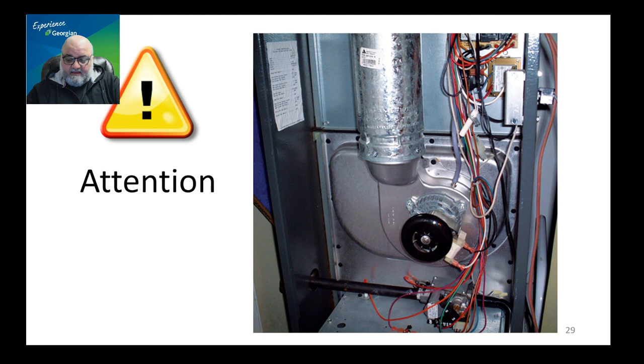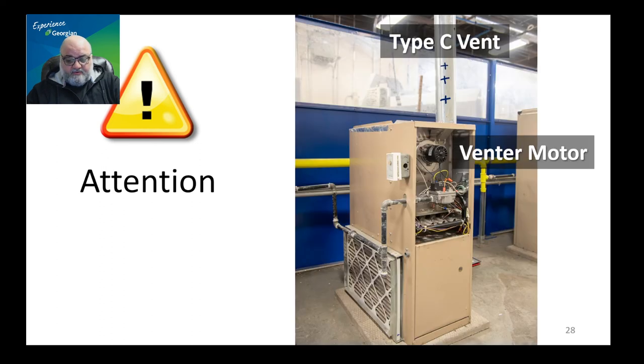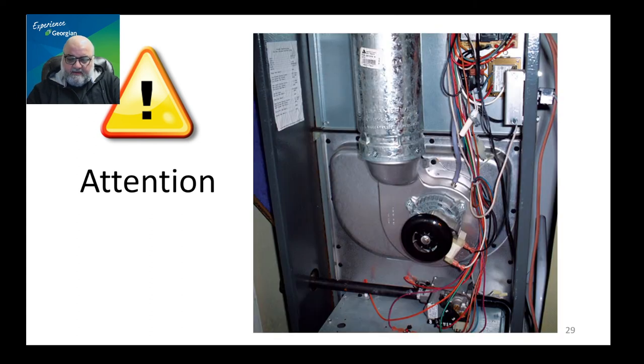There is also an example of type B vent here. The reason you see those two types is that, first, no more of that combination is done anymore. But during the process of developing better appliances, there were certain phases where venter motor appliances were certified to be used with type B vent. This brings us to the idea of a fan-assisted burner — and note this is not about mechanical draft, natural draft, induced draft, or forced draft. This is about the burner itself.